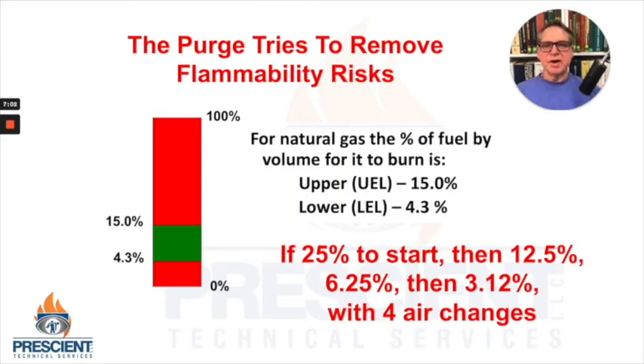So the purge tries to remove flammability risks. It tries to think to itself, well, if there was some type of a leak into the firebox while this equipment has been down, possibly the firebox is full of gas, and the thought of getting 4 complete air changes is trying to get the possible LEL down below a level where there would be ignition when the pilot starts. In Europe, there are more air changes required in their standards.